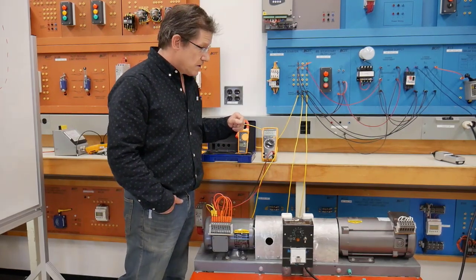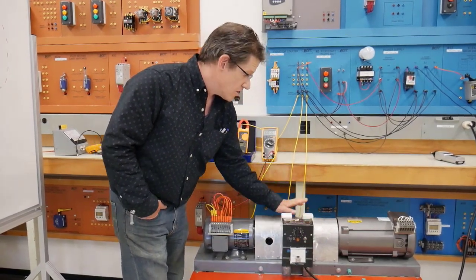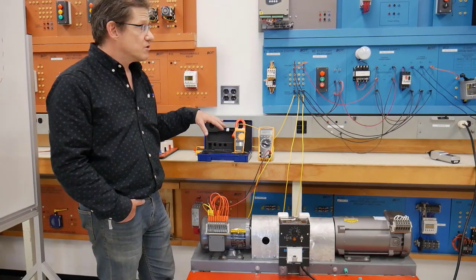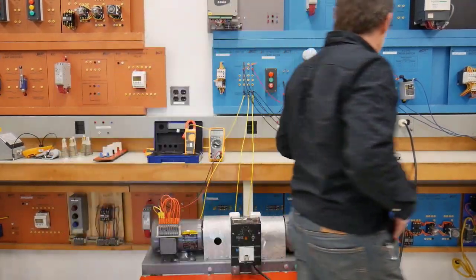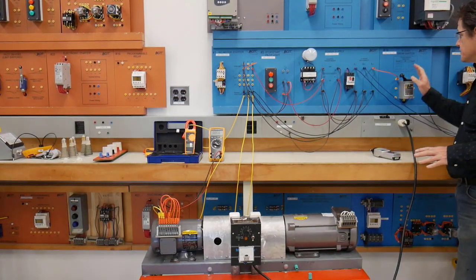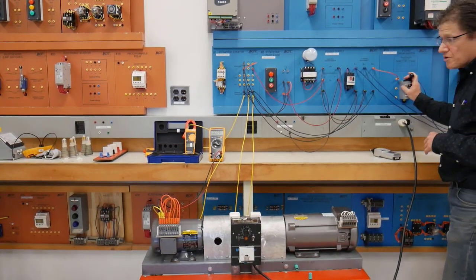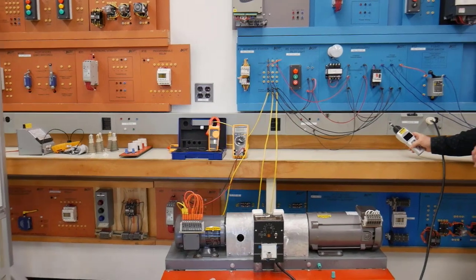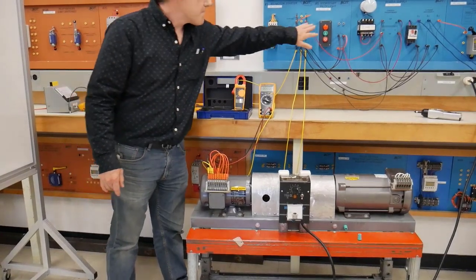Now we're going to go ahead and start it. Right now our eddy current brake is off, so this first reading is going to be a low load situation. Also, over here we have our drum switch that we're going to use to create our single phase conditions. Right now it's closed. We'll bring it open and it'll disconnect line 3 from our motor, and we'll have that single phase condition occur. For now, we'll leave it on. We'll also check out the RPM later on when it's loaded. Shall we give her a start?